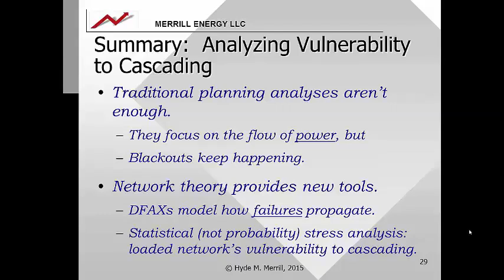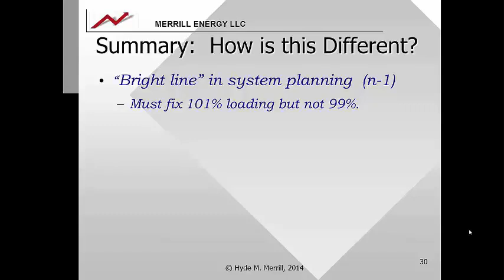In planning, I'm going to simplify things a bit, but there's a bright line in system planning. By NERC criteria, which have the force of law in the United States, a system has to be planned to N-1 conditions. That is, if the worst contingency will cause a line to overload, then the system has to be fixed. And the bright line says that if, under the worst contingency, the system is loaded to 101% of its capacity, of its rating, then you have to fix it.